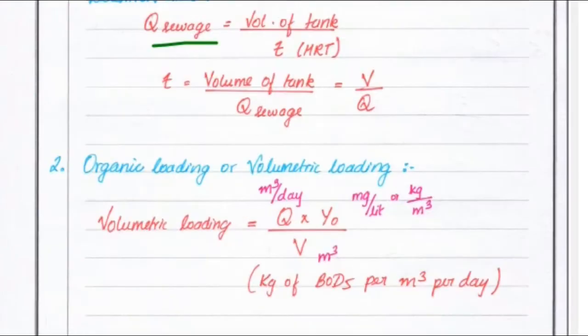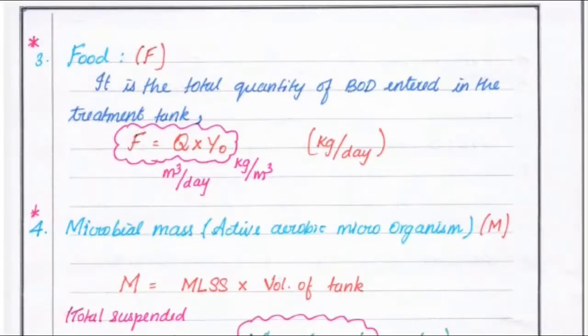Next is organic loading or volumetric loading. Volumetric loading equals Q, that is discharge, into Y-naught divided by V. Q is in terms of meter cube per day, Y-naught is in milligram per liter or kg per meter cube, and V is in meter cube. So the unit is kg of BOD5 per meter cube per day.